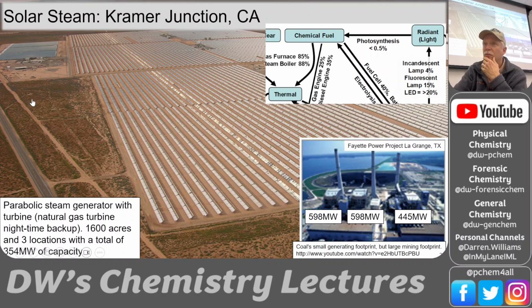Yeah, and water's a big problem. Water's a bad actor in a sense because it's hard to keep it pure. Whenever you flash something to steam, anything that's not water precipitates out, and that's called scale. So in order to get this water to reliably evaporate, it's going to be depositing all its soluble metals. Calcium is a big actor because calcium oxide precipitates out in all boilers and gets on the heating elements—we see it as water spots. When you wash dishes and let them air dry with hard water, you'll see water spots; multiply that by a billion, and that's what you'll have inside these tubes. It's a real problem—water's the Achilles heel for a lot of these things, even our steam boilers.